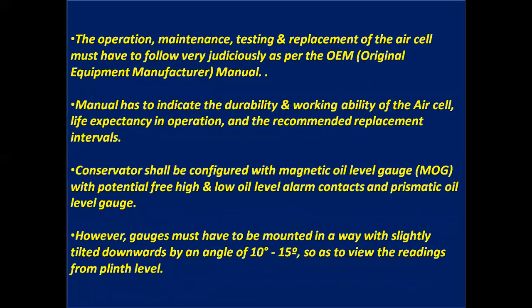The operation, maintenance, testing and replacement of the air cell must have to follow very judiciously as per the OEM, that is original equipment manufacturer manual. Manual has to indicate the durability and working ability of the air cell, life expectancy in operation, and the recommended replacement intervals. Conservator shall be configured with magnetic oil level gauge with potential free high and low level alarm contacts and prismatic oil level gauge.